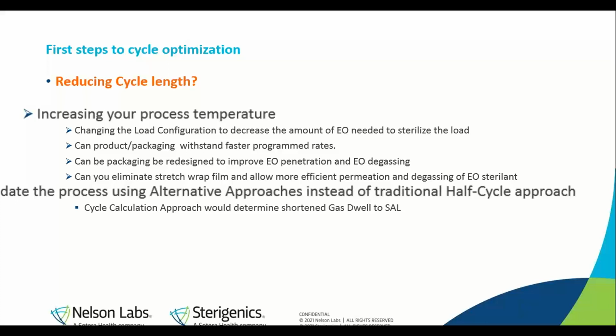And also pointing out further down the list, the opportunity today with the fact that the FDA issued in 2019 an innovation challenge to the medical device industry, to look at utilizing existing alternative approaches for validating the process instead of the traditional half-cycle approach. There are several alternative approaches where one of the benefits would be to potentially reduce the overall cycle time by reducing the gas exposure time necessary to sterilize your product. Don't get me wrong, in the end, these alternative approaches will still deliver a sterilization process providing the minimum sterility assurance level required for your sterility claim. It's just different tools in your toolbox.